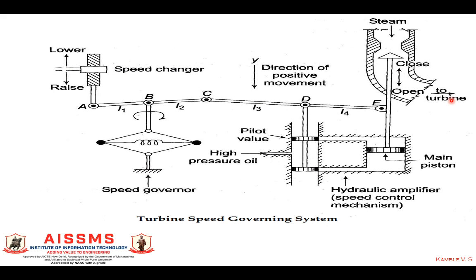So this is the actual working of ALFC. Due to load conditions, if the generator speed decreases or increases, that change is sensed by the flyball mechanism. According to the speed change, the flyball moves inward or outward, and the linkage mechanism operates accordingly, moving the steam valve in the closure or open direction. This controls the steam flow, which controls the speed of the generator — that is, the active power is controlled, and when active power is controlled, it controls the frequency. Thank you.